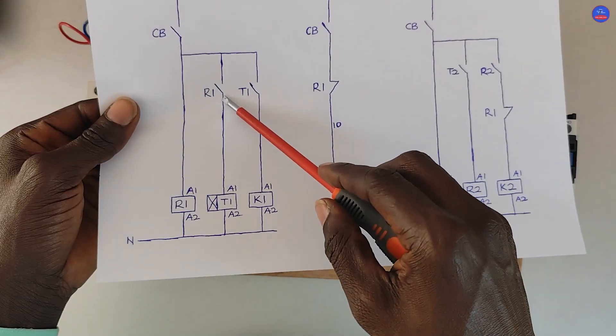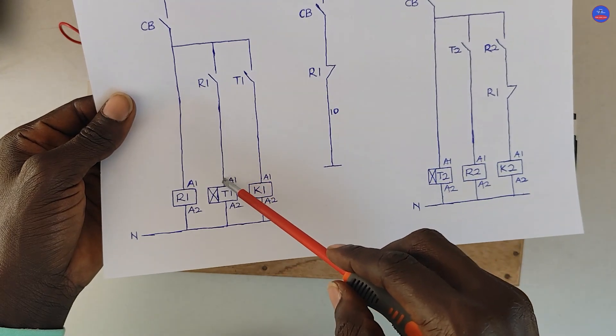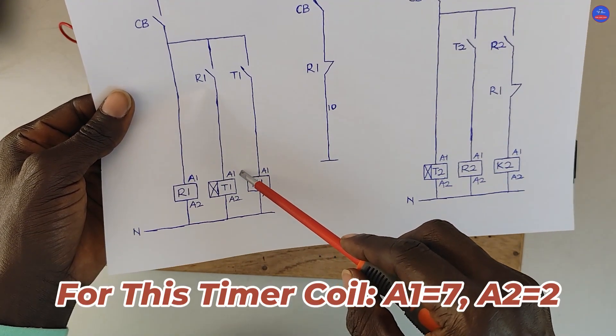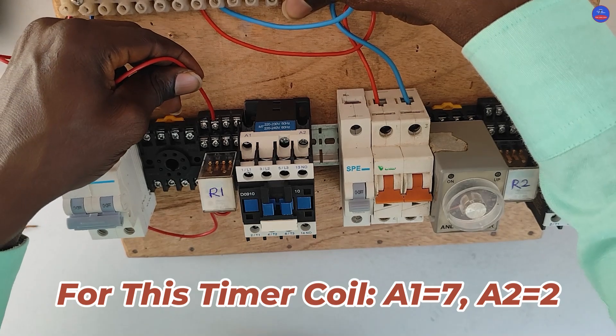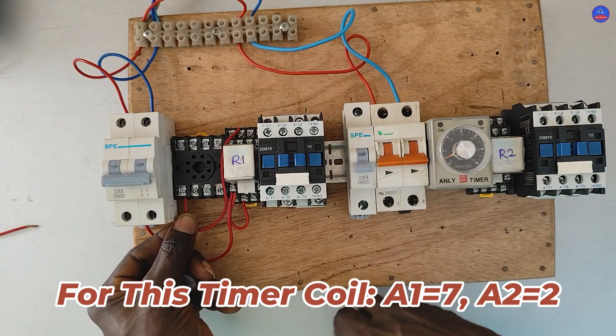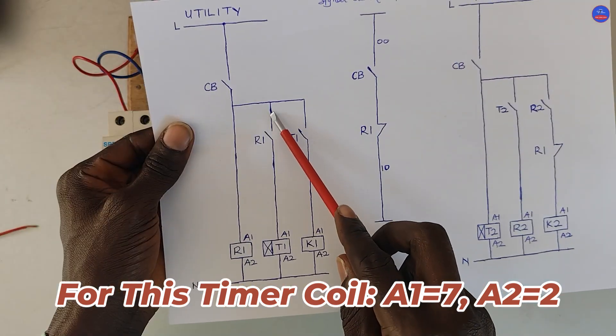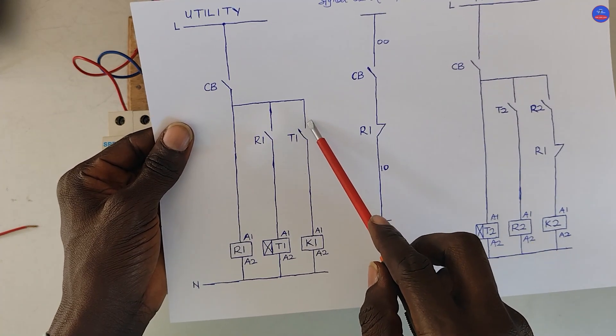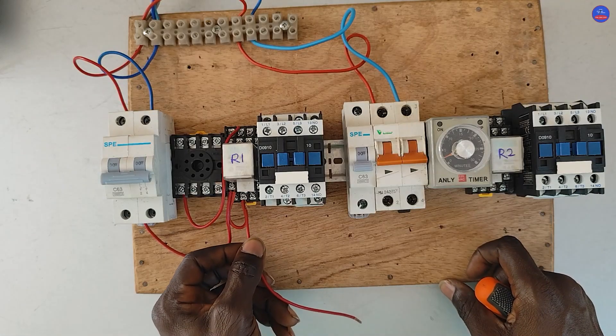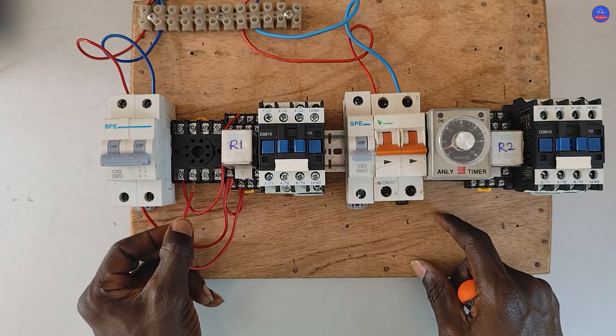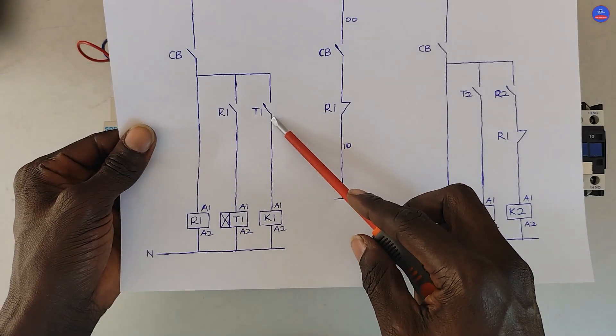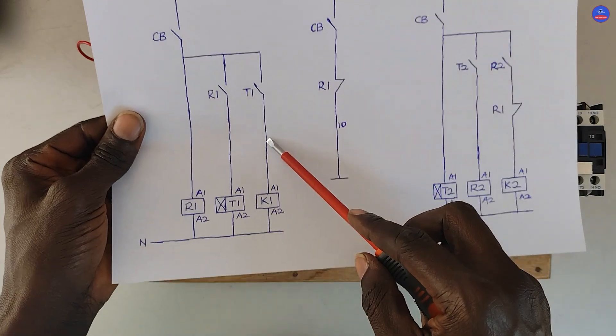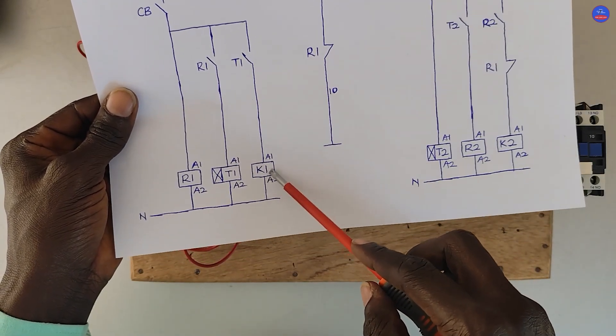From the other side of the contact, it connects to terminal A1 on the timer — this terminal A1 is terminal 7. We tap from the relay other side to the common terminal of this timer, which is terminal 8. From the other side of the open contact, that is terminal 6, it goes to terminal A1 on K1.